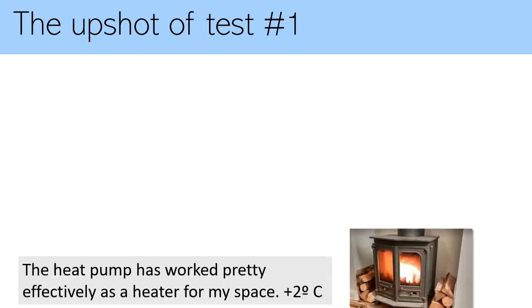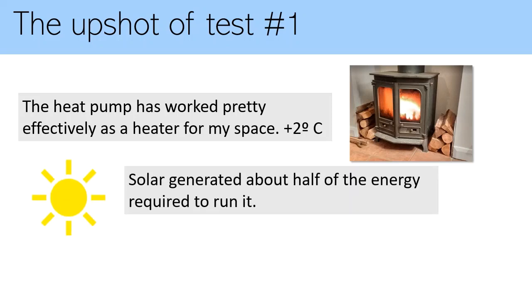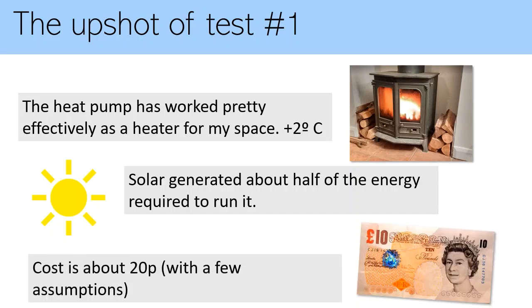The upshot of test one: the heat pump actually worked pretty well as an effective heater for the space — a 21-foot by about 12-foot living room diner — gaining plus two degrees Celsius over the course of the hour, bringing it from 18 degrees to a comfortable 20 degrees. The solar generated about half the energy required to run it. If we assume the solar is just being used to power the heat pump, that's about half the cost covered, which at about 39-40p per kilowatt hour equates to about 20p for running the aircon for the hour.